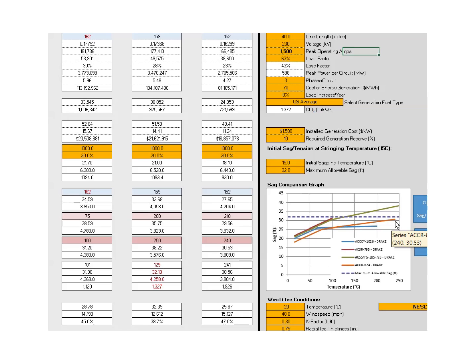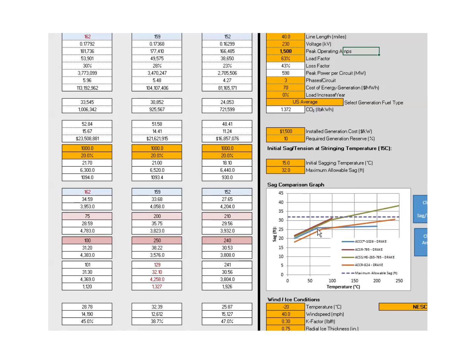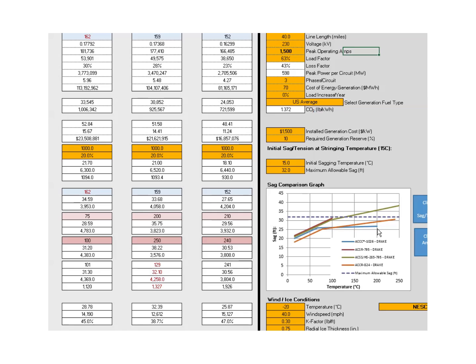3M is much improved over ACSS. So that would get you to full capacity. But again, you're operating up close to 240 degrees C at max capacity. While ACCC has a thermal knee point at about 65 degrees C initially, at which point the aluminum relaxes its load and sends the entire load to the core that's very dimensionally stable. So you have very good clearance capabilities, which represented on a new line would allow you to put in a tower that was about 5 or 6 feet shorter than the initial tower used for ACSR conductor. And again, it operates at much cooler with still a higher degree of amperage.